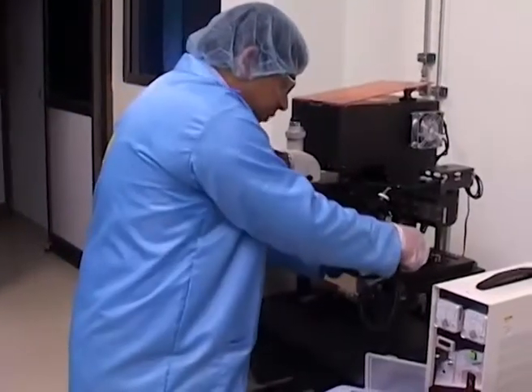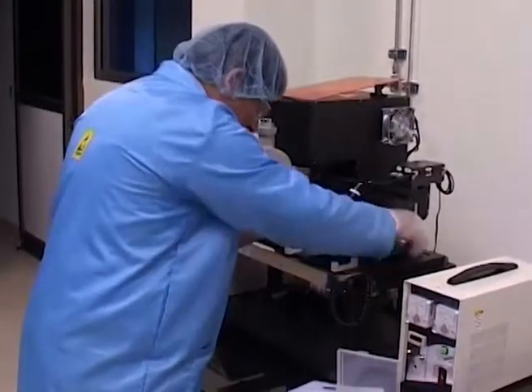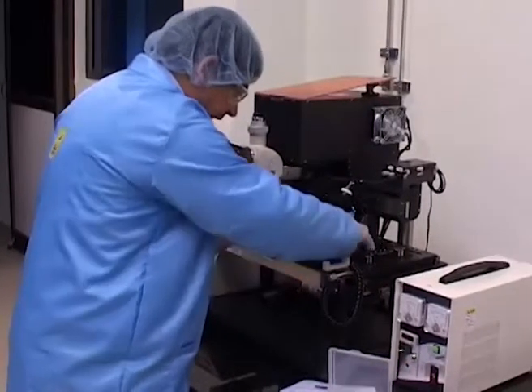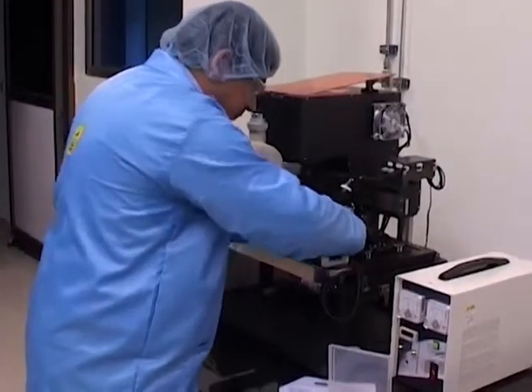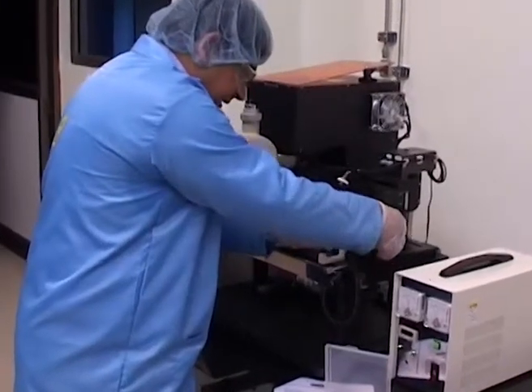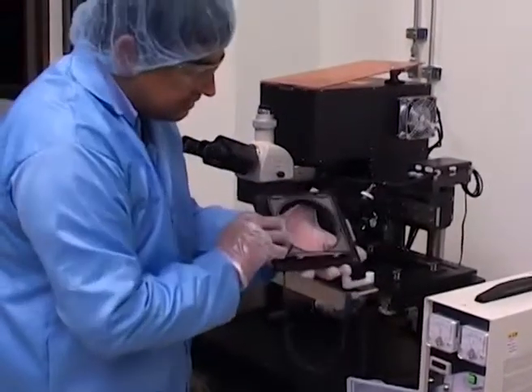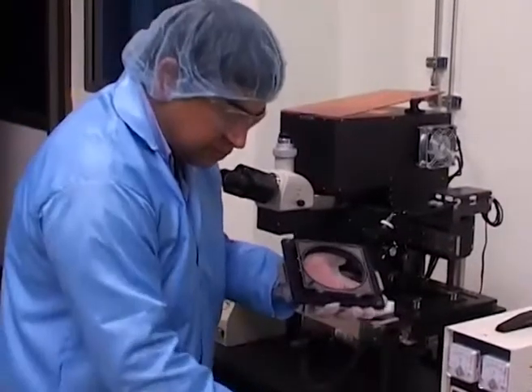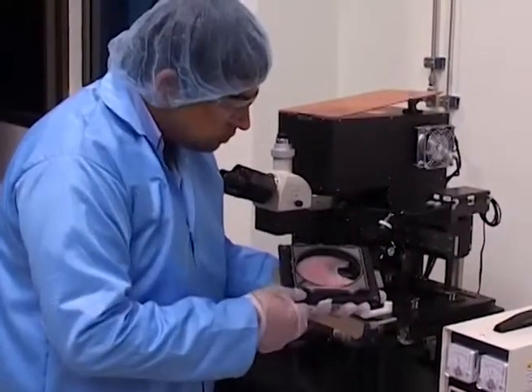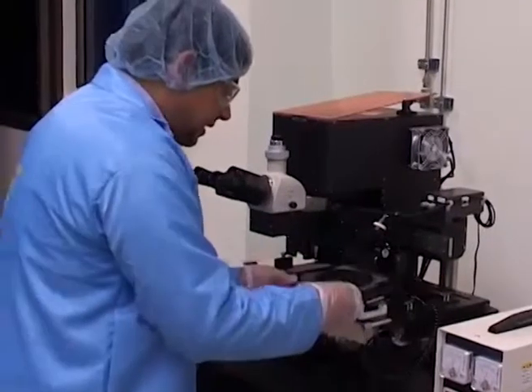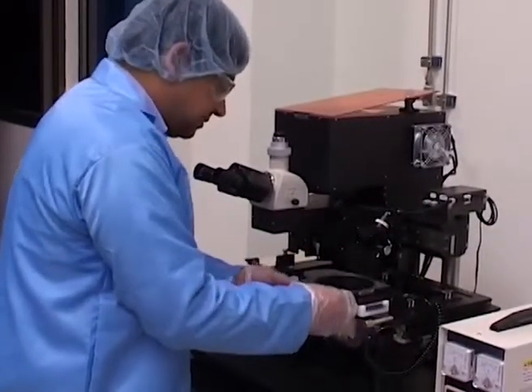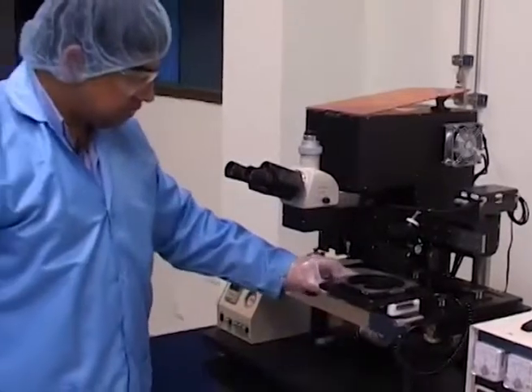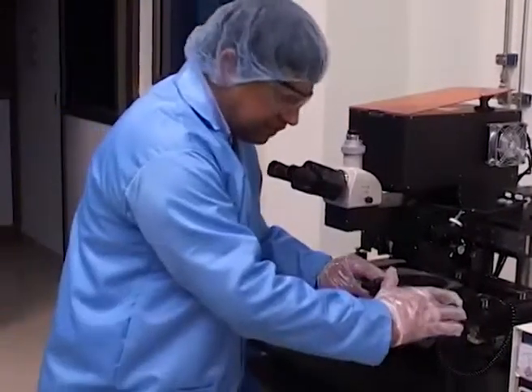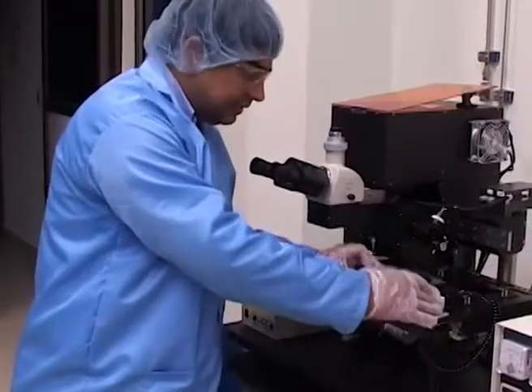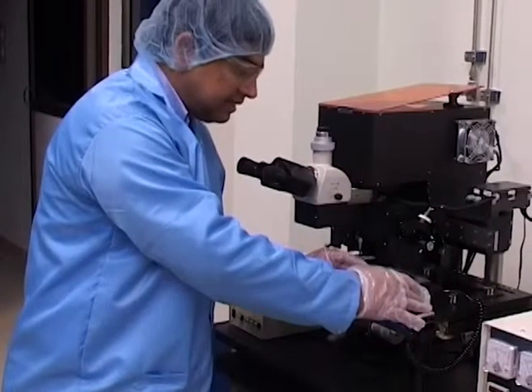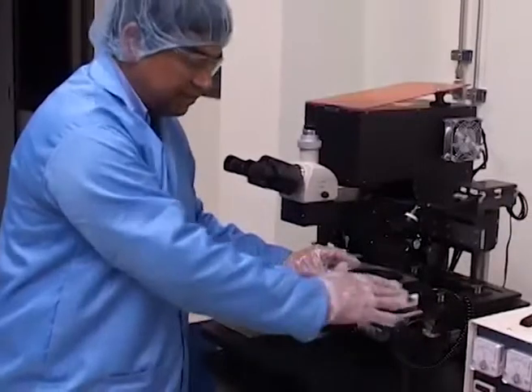So in order to do that, what we do is loosen these particular points here. There are four such screws, and then we slowly pull out this part from the machine, and essentially, as you see, this really is the surface which holds this particular hard mask. There is a stand for this mask loading. You have to put it right in that particular spot. It's like a jig, and it ensures that there is no unnecessary toppling or falling down of the mask holder.